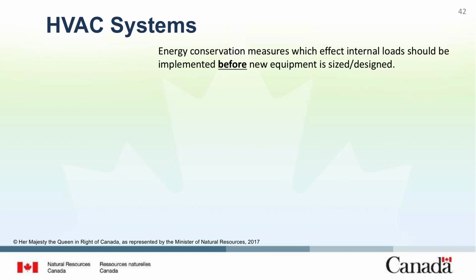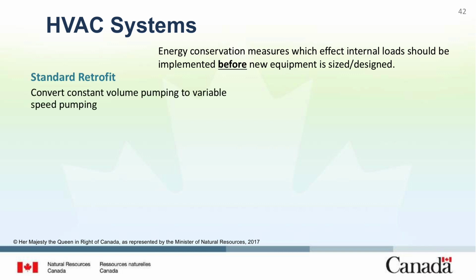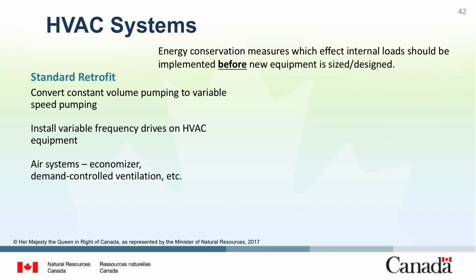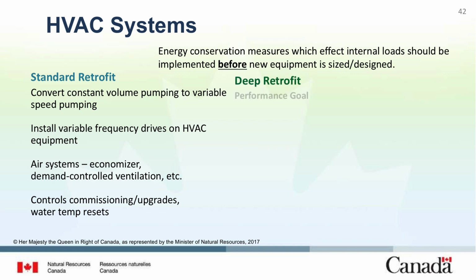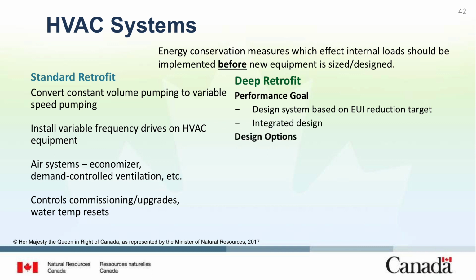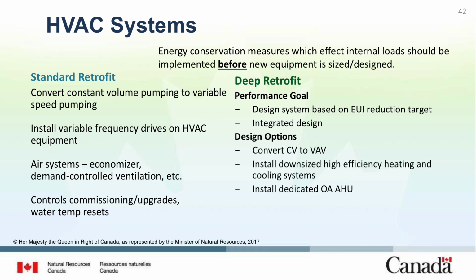Standard retrofit items include converting constant volume pumping to variable speed pumping, putting in variable frequency drives, and HVAC controls. Deep retrofits take an innovative approach to either setting a performance reduction target or fundamentally changing the HVAC system that was there before. Some examples include converting constant volume to variable air volume, downsizing the equipment that you're putting in, and then these last four are innovative ways that HVAC systems are being implemented in new ways that haven't been seen in the past 30 years. There's dedicated outside air with energy recovery.